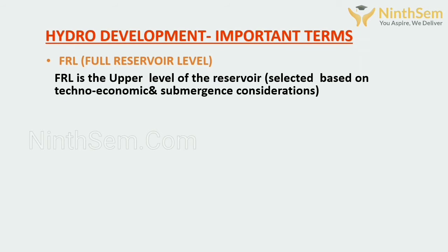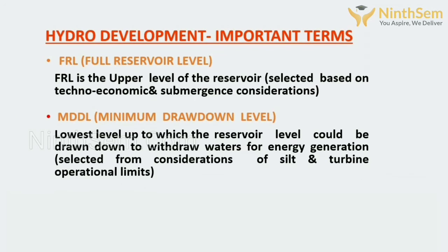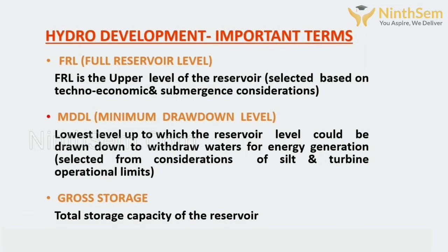Hydro development important terms are as follows: FRL, full reservoir level, which is the upper level of the reservoir; MDDL, minimum drawdown level, the lowest level of the reservoir that can be used for the energy generation. Gross storage is the total storage capacity of the reservoir.